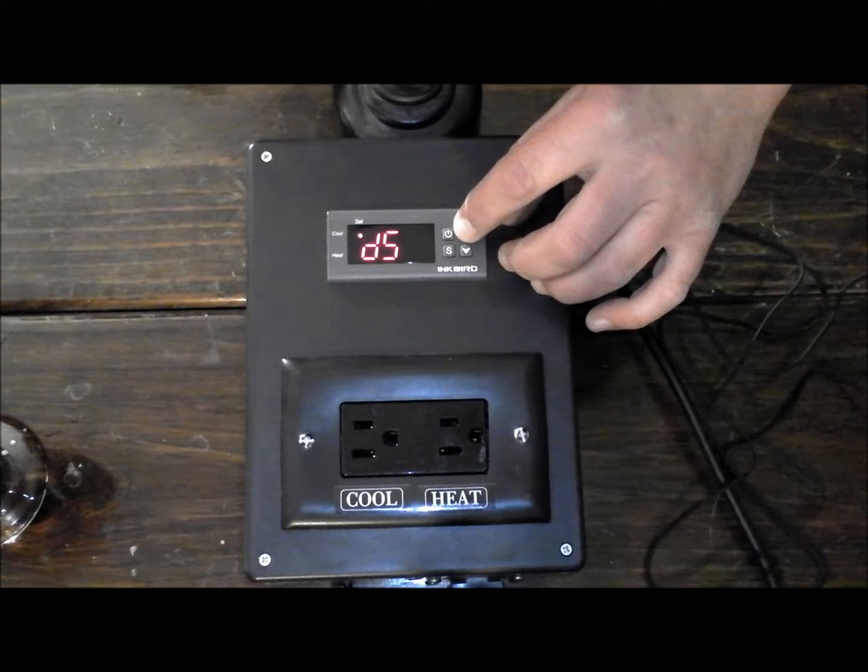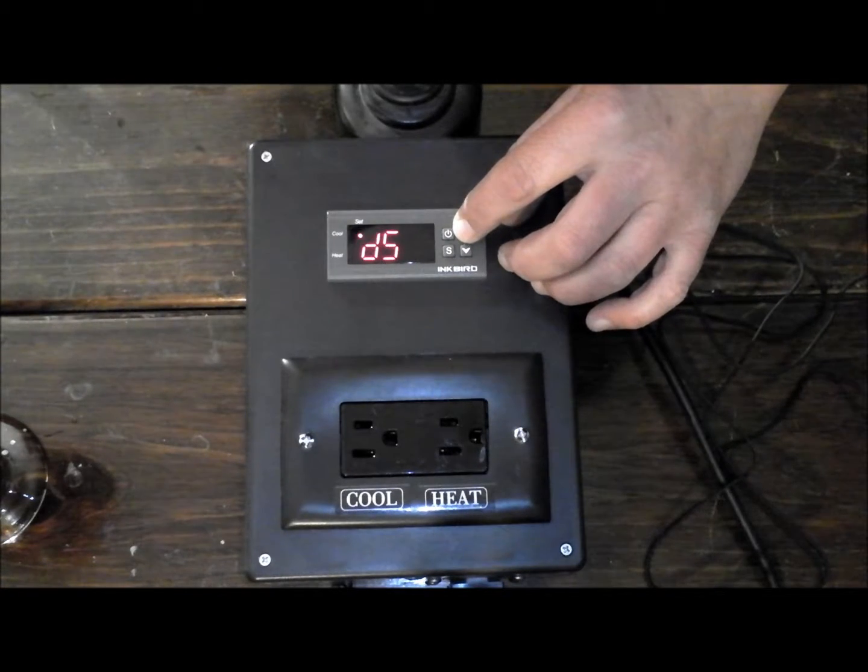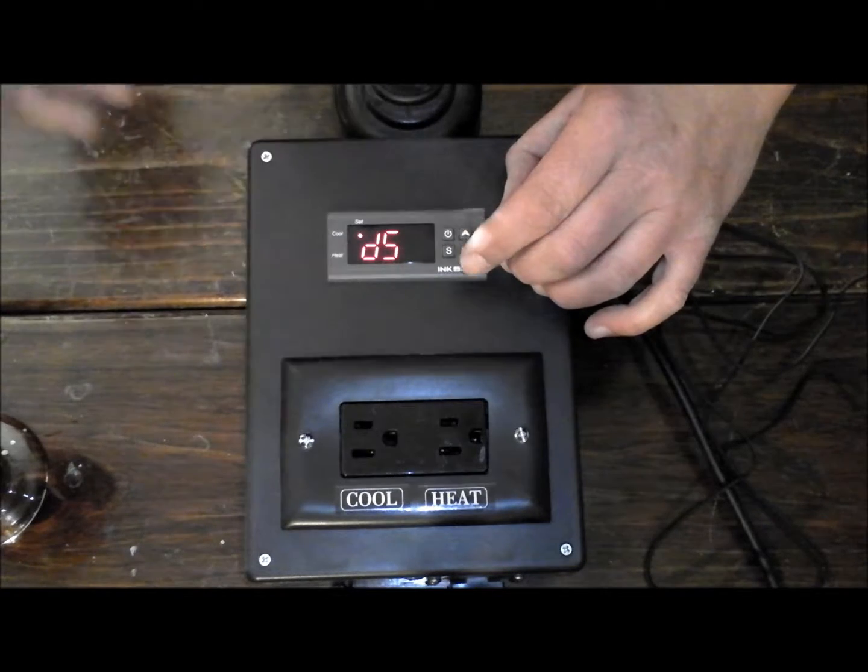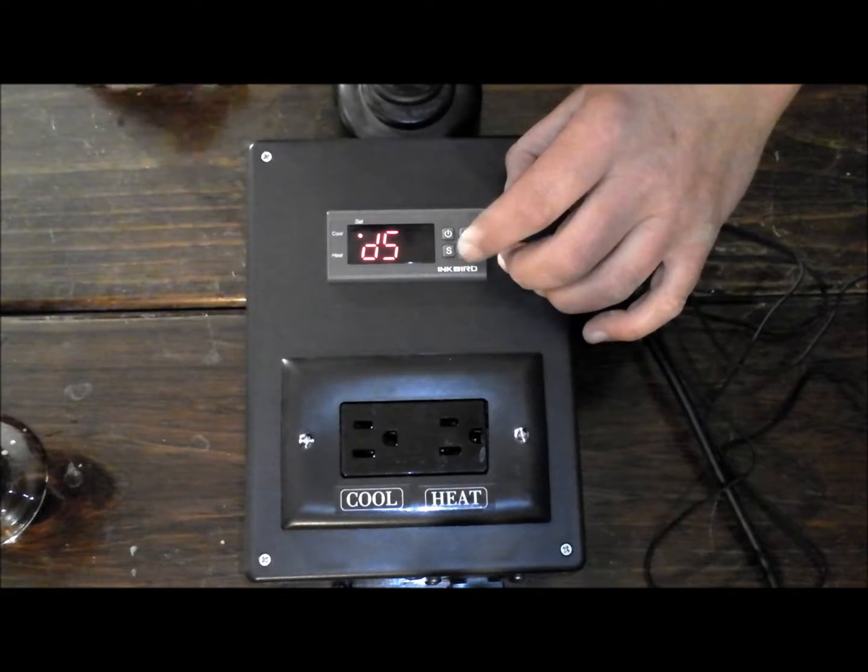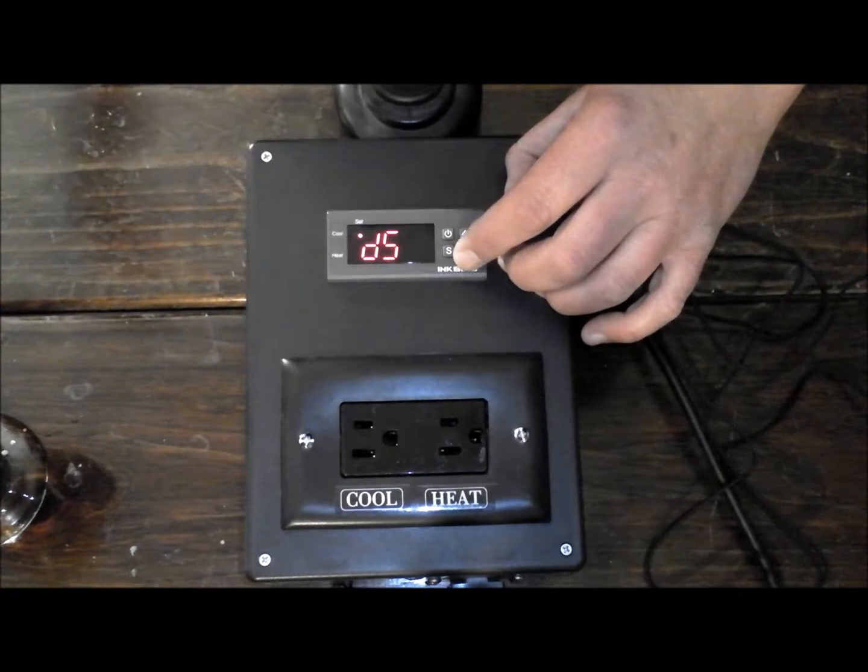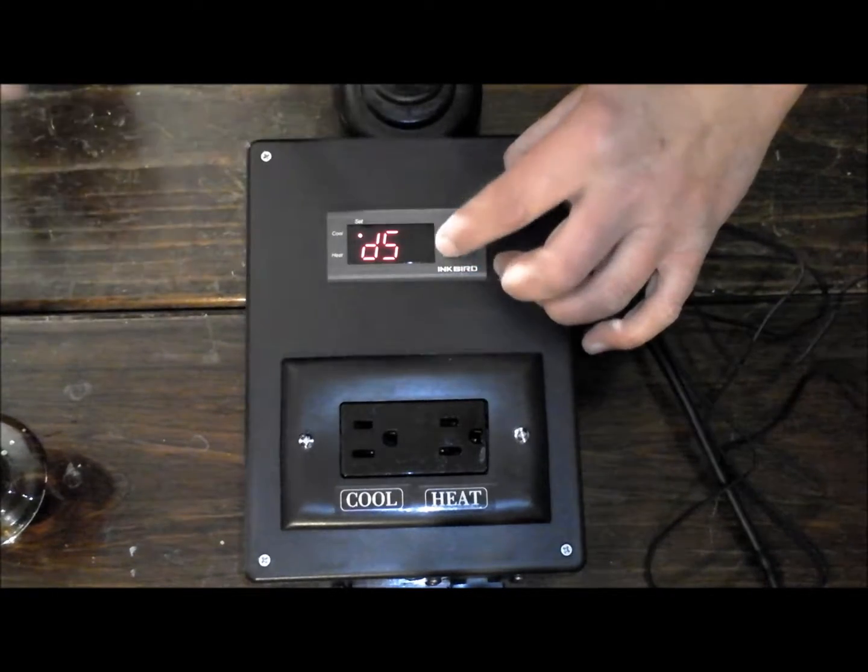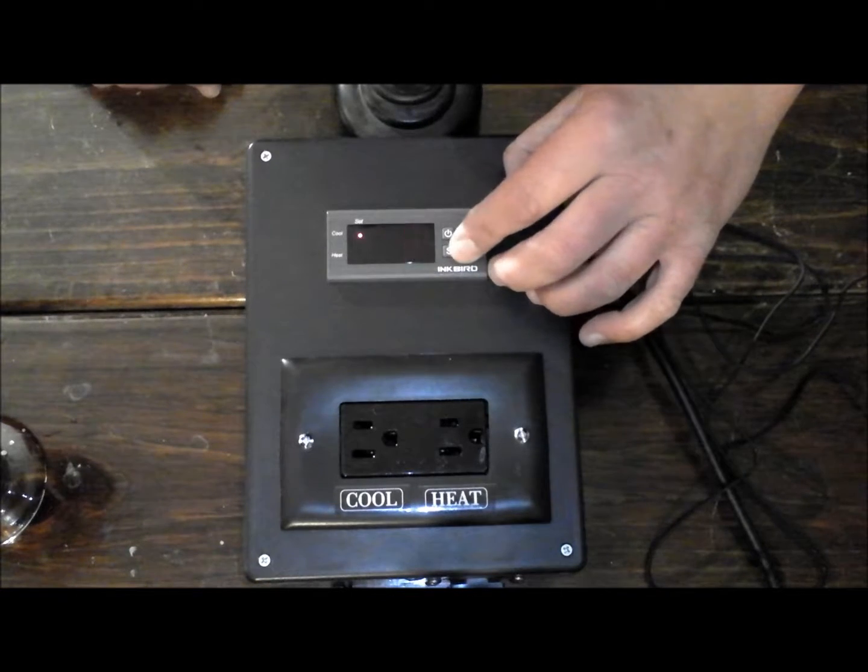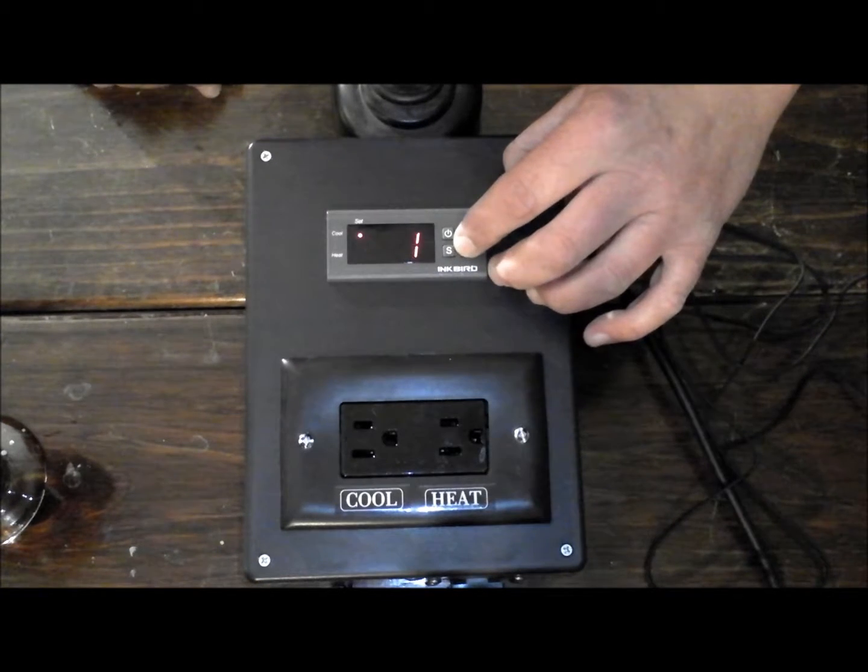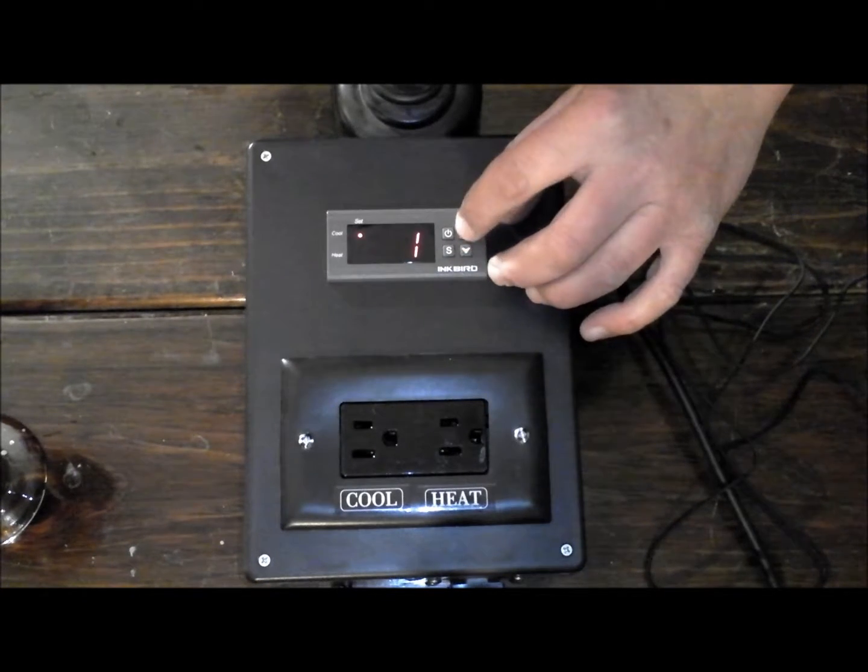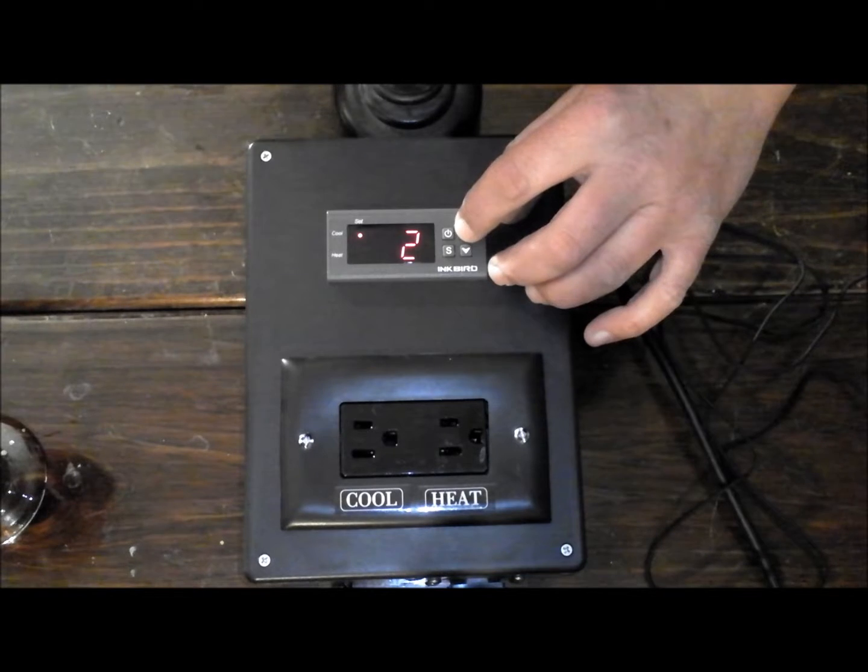The next one we have is the DS, which is your difference value. In other words, how many degrees from switching from heat to cool. Right now it's set for 3 degrees, you can go down to 1 or up to 30.